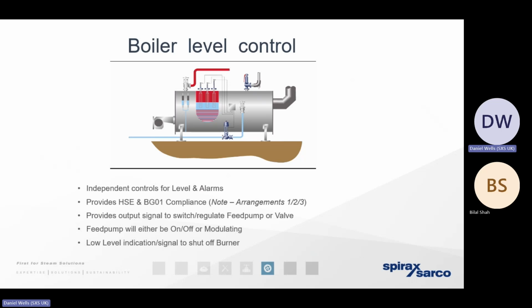So in order to control the water level, we're going to need a variety of different level controls, sending a signal to a pump. Ideally, we'll be operating the boiler with a modulating feed pump that's constantly circulating a ring main of high temperature hot water around the boiler house. And we'll have a capacitance level control probe, which means that that boiler is capable of operating at a consistent water level. The water coming into the boiler will be in equilibrium with the steam leaving the boiler.